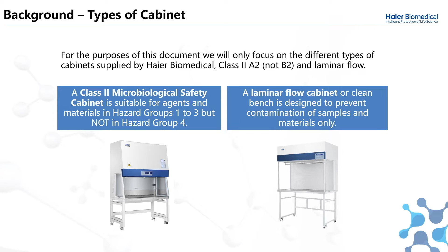The class 2 microbiological safety cabinets we offer are primarily recirculating cabinets. A recirculating cabinet will take some of the air that's circulated around the cabinet and exhaust it. The rest of the air is recirculated internally through a ULPA or HEPA filter to clean the air. The clean air then flows down onto the subject to make sure it is kept clean and free of contamination. This air is then recirculated and again either exhausted through a single or a double HEPA, depending on the model, or back through the ULPA or HEPA downflow where the cycle continues. These are very popular versions of cabinets as they require no ducting, which can be expensive, and it can save the customer money.